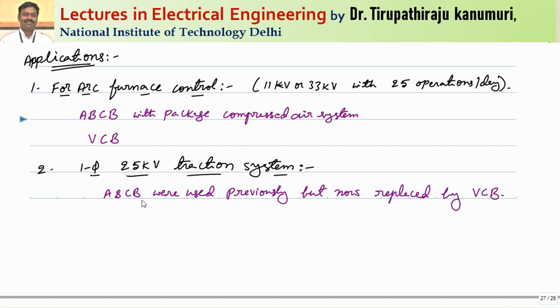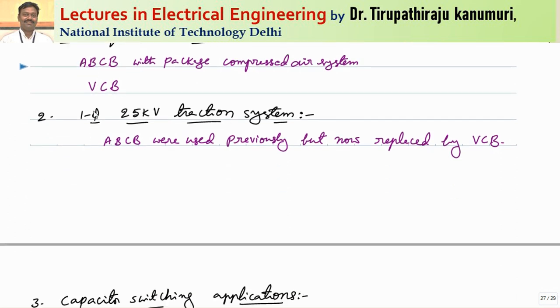For arc furnace applications, the furnace is designed to operate at either 11 kV or 33 kV with about 25 operations per day. When there are many operations per day, the disadvantage of oil circuit breakers is that the oil gets decomposed into gases and carbon is formed, so carbon deposits degrade the dielectric property. For frequent operations, oil circuit breakers are not preferred. In practice, we go for either air blast circuit breakers (ABCB) or vacuum circuit breakers. Nowadays the trend is vacuum circuit breakers for arc furnace applications.